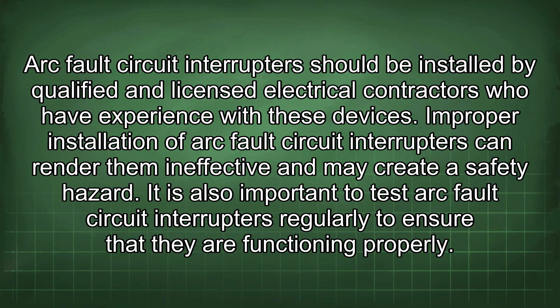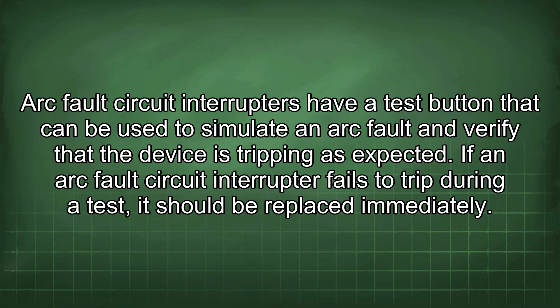It is also important to test arc fault circuit interrupters regularly to ensure they are functioning properly. They have a test button that can be used to simulate an arc fault and verify that the device is tripping as expected. If an arc fault circuit interrupter fails to trip during a test, it should be replaced immediately.